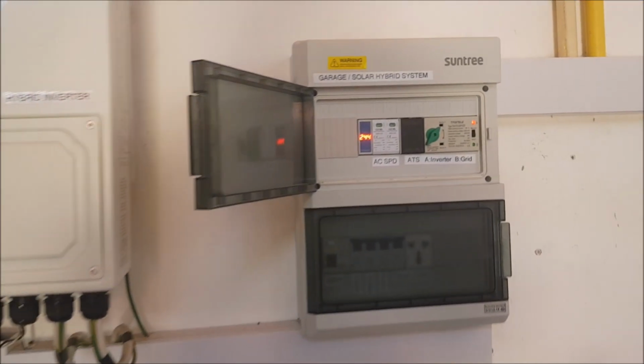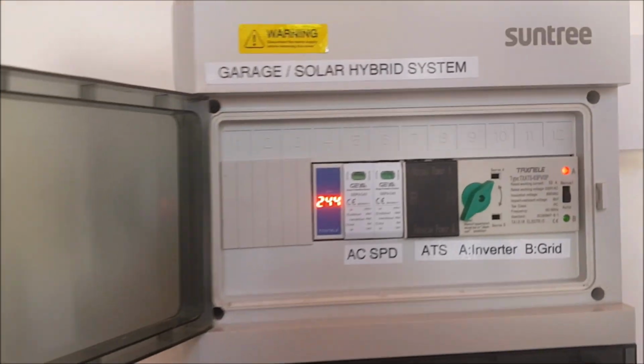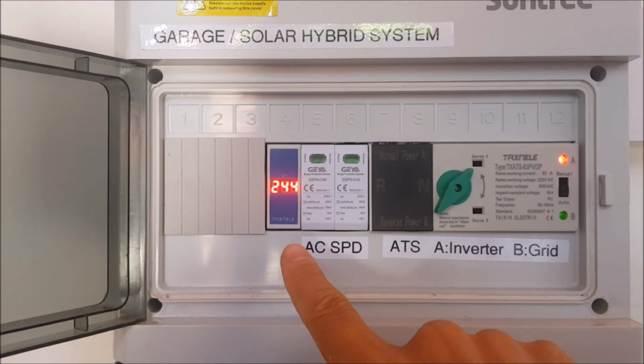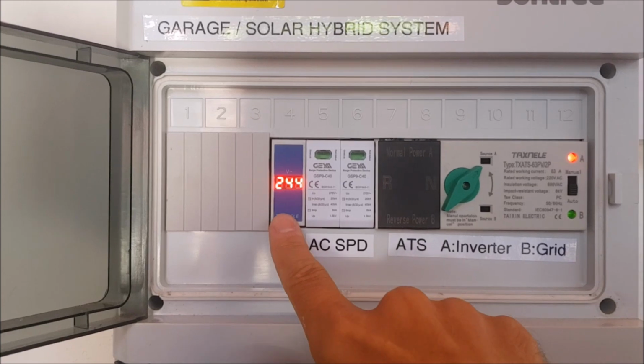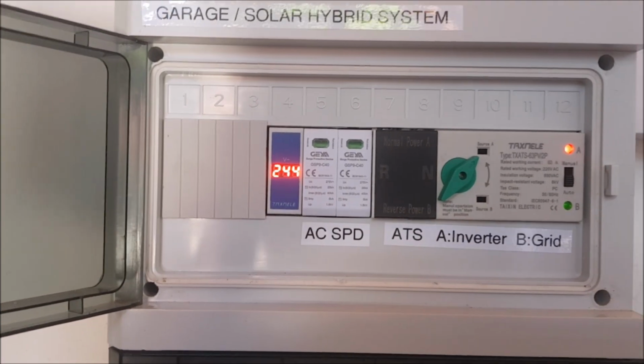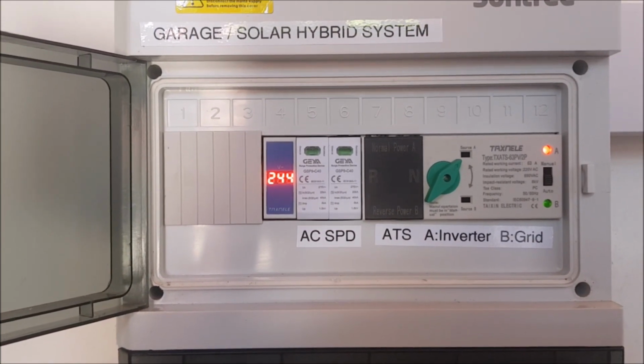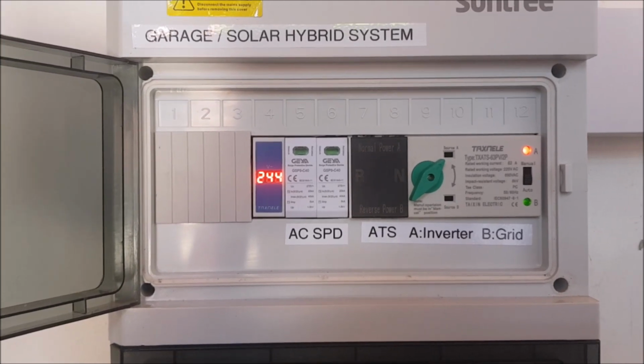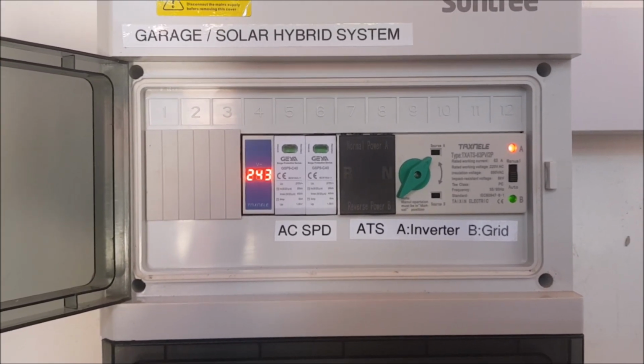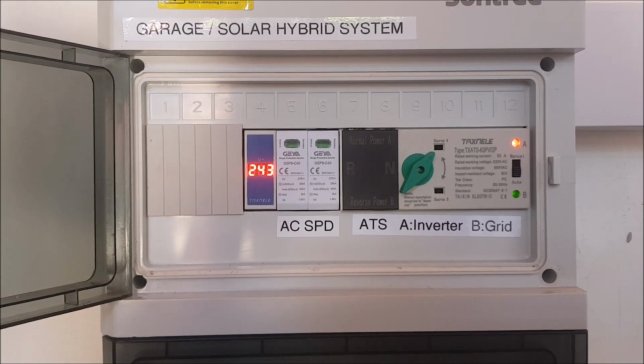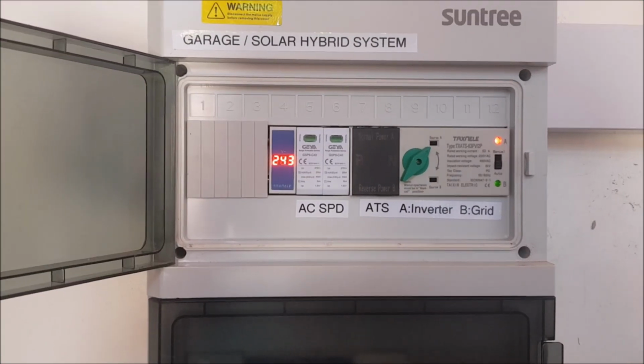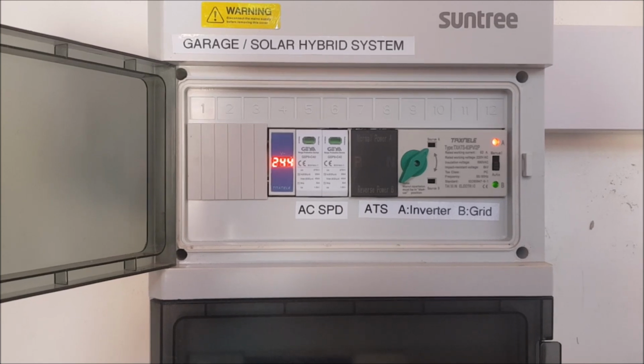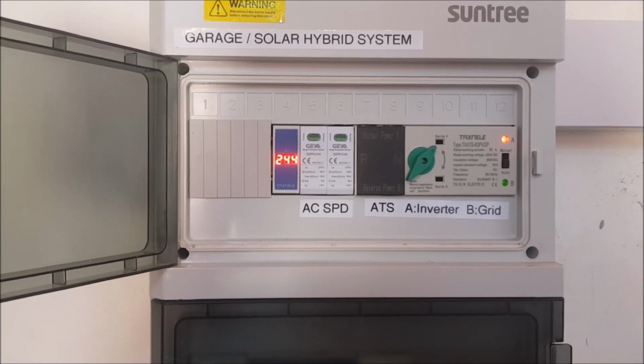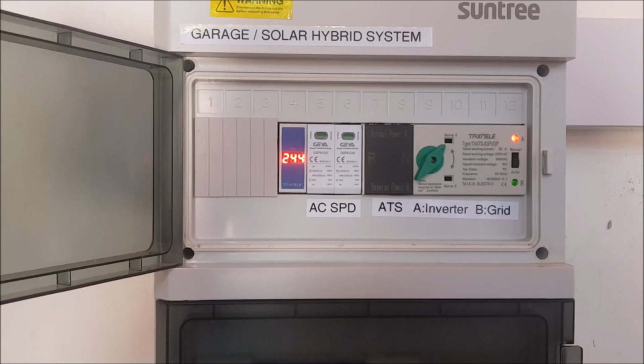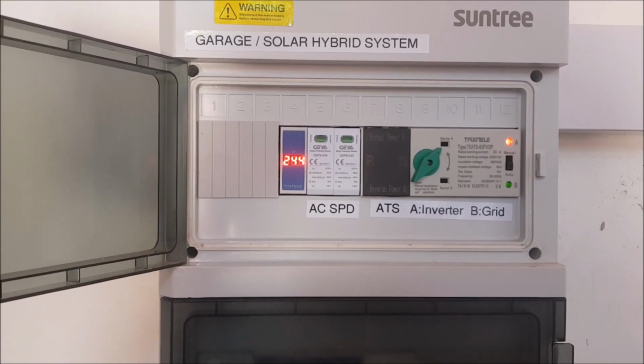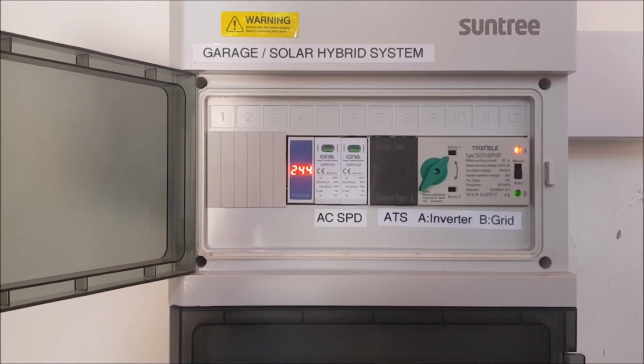Here at my hybrid inverter, we can see the distribution box. Here you see a meter reading 244, that's voltage. So we have 244 volts here in the garage, where all these grid tie inverters are feeding in. Nominal voltage here in Thailand is 230 volts. 244 is quite high, of course, but for most of you this will still seem quite normal.